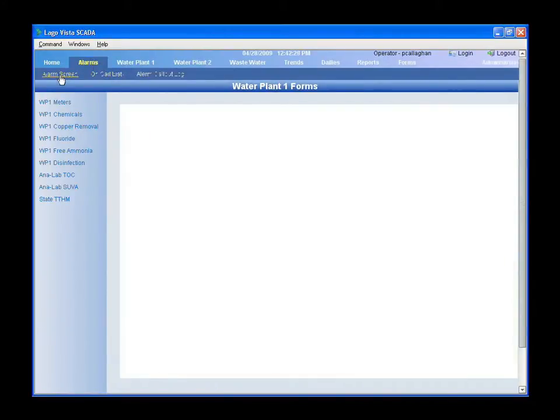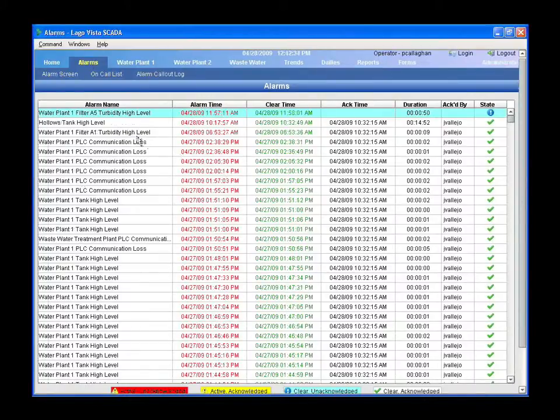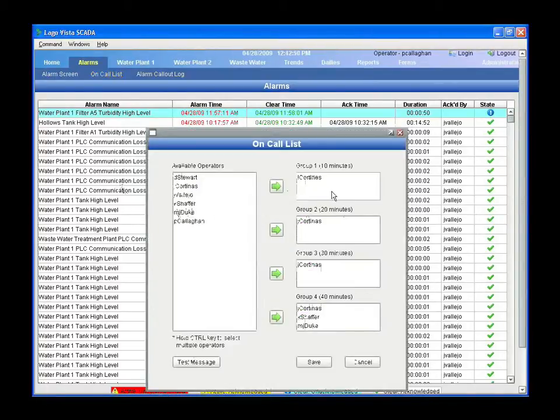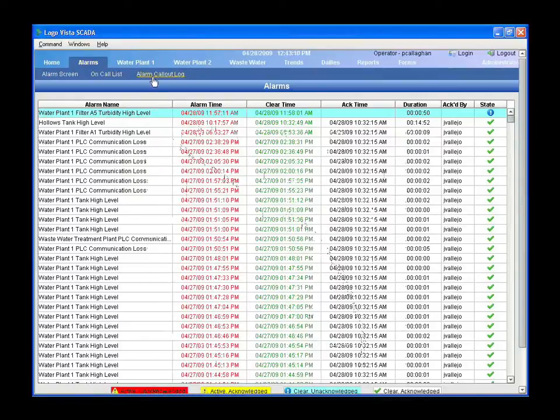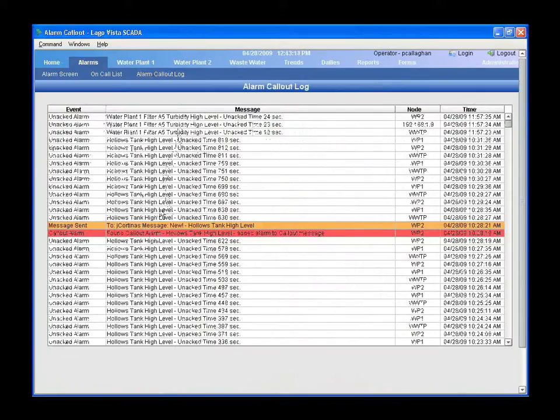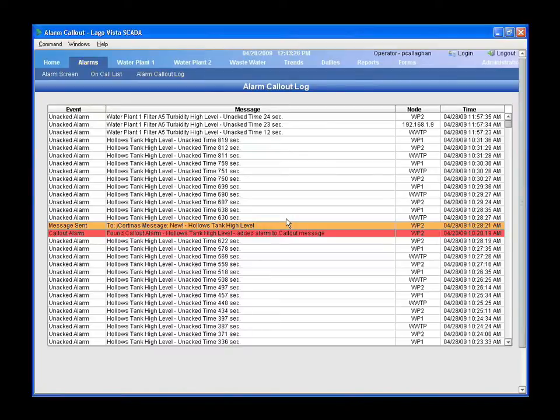On the alarming screen, the system will call out for alarms, and we added text messages. Operators select who's on call and add them into callout groups. When an alarm comes in, 10 minutes later that person gets a text message. 20 minutes later, if the alarm is not acknowledged, the people in the next group receive a text message — and so on down the list. I can also look at the callout log, which shows what happened and confirms that a person received a text message, so if something never got answered we can go back and find out what happened.